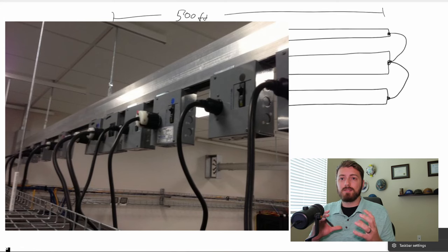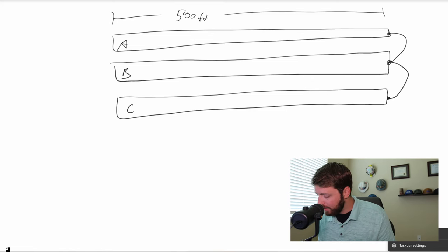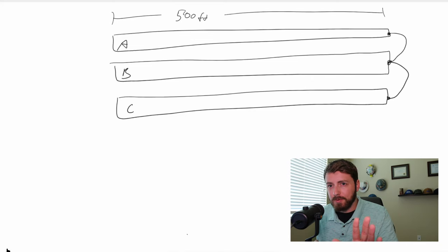you're going to take a tap box. It's got a breaker in it. Borrow that from the EC, borrow it from the customer when you guys are doing commissioning. Take the breaker out and then just put jumper cables in to jumper the buses together. So you've got a movable thing that you can slide in and out of each bus duct end that you're going to be working on. It's a really easy way to do it. Highly recommend.